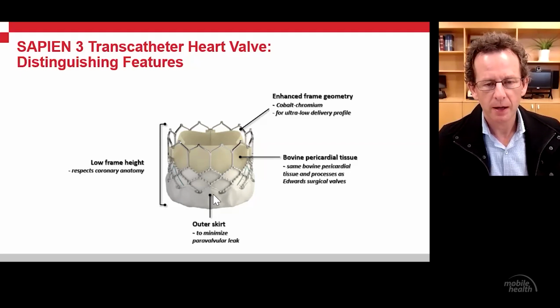There's a skirt around the outside of the valve, and one of the problems with the first generation and second generation valves is that there was a bit of a leak outside the valve, what we call perivalvular regurgitation, so a leak from the aorta going back into the ventricle. This is obviously a circular structure, and the annulus of the aortic valve is not a perfect circle, and there are little bits of calcium and things like that, so there are little crevices for blood to leak back through. And this skirt expands into those and almost excludes any leak around the valve.